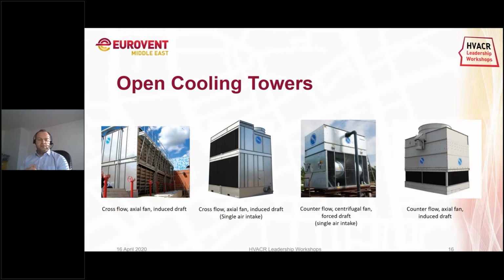First of all, you can have the group of the open cooling towers. You have the cross-flow cooling towers. In these ones, the air is coming from the sides and the water is coming from the top. You can have it with axial fans. You can also have cross-flow cooling towers with single air intakes. You have the counterflow cooling towers, where the air is coming from the bottom and the water is coming from the top. So you see there is a broad range of products.